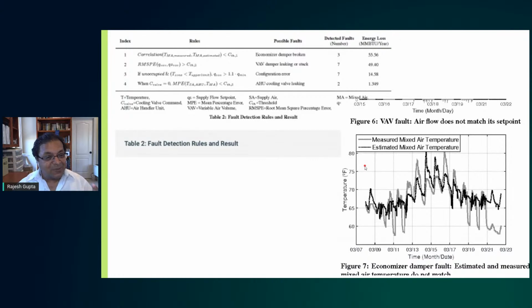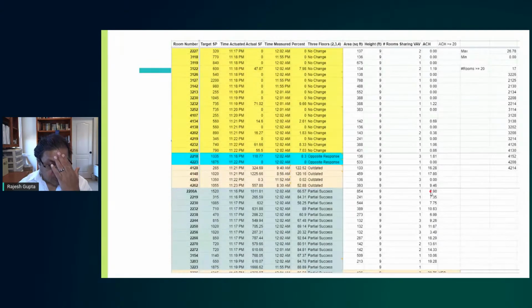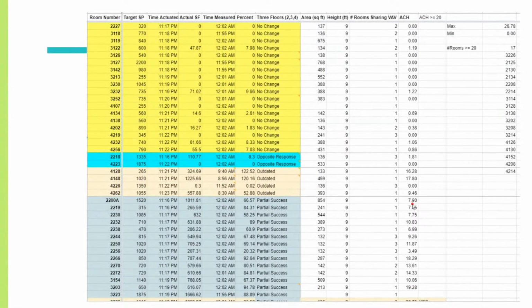But even much more interesting was the ability to discover that, look, the airflow is showing me this much air going in, but the VAV is giving me a different number, and it is not adding up. It is not adding up because there is a fault. There is a damper that is stuck open or closed. So we started discovering faults in the system automatically. And in fact, when we wrote a program, there are something like 250 rooms in this particular building.